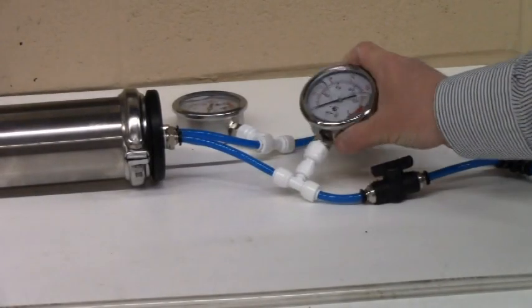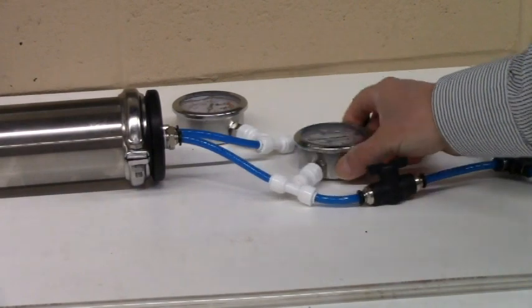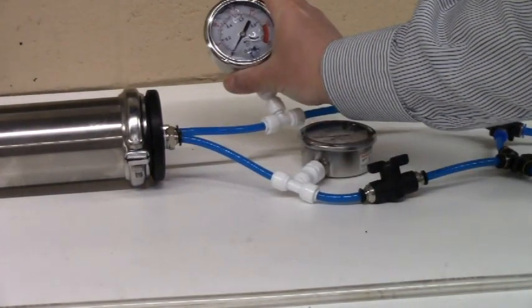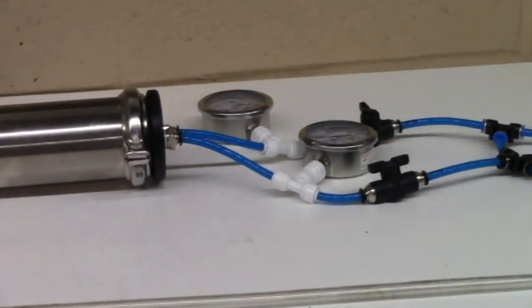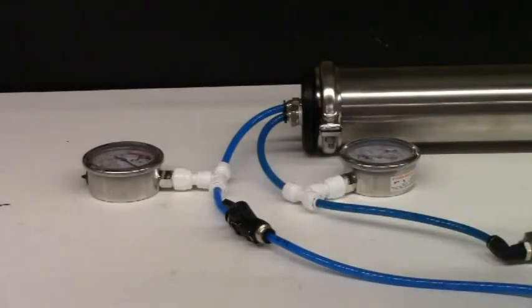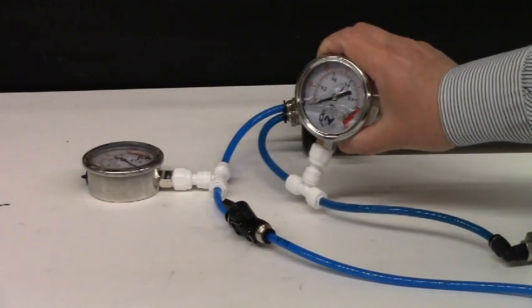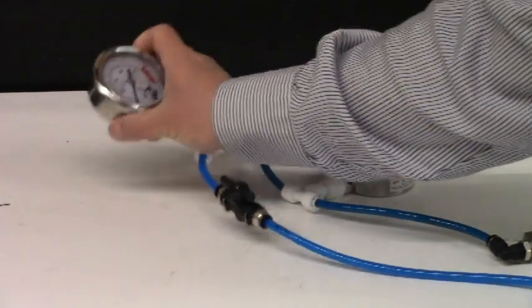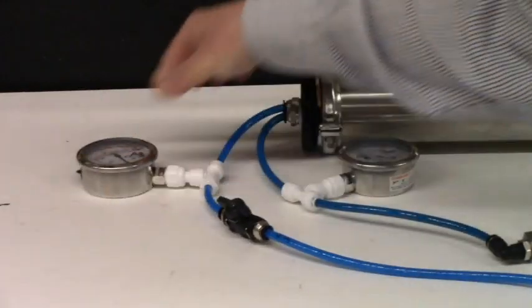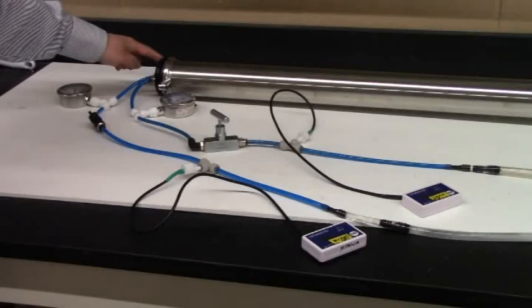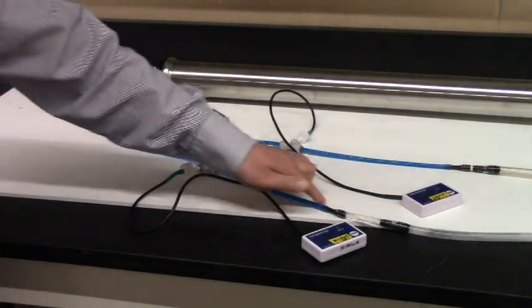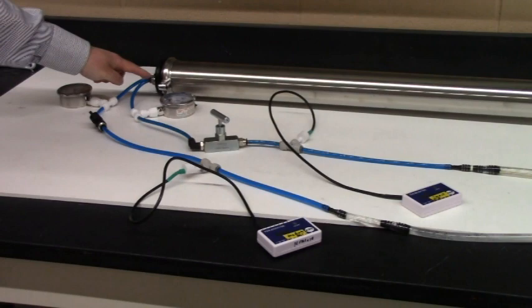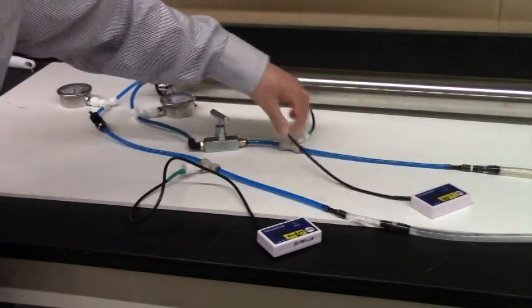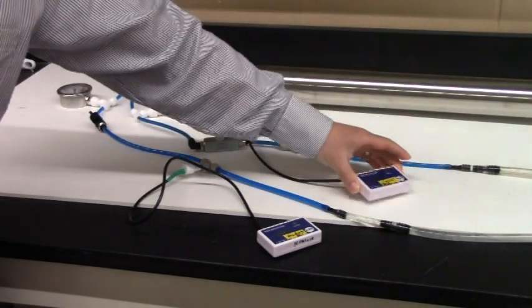There are two pressure gauges at the front end of the filter. One is for filter inlet line and the other for the backwash inlet line. There are two pressure gauges at the back end of the filter. One is for the reject line and the other for the filtrate line. There are two TDS meters at the back end of the filter. One is for the filtrate line and the other for the reject line. The TDS meters can qualitatively monitor salt concentrations.